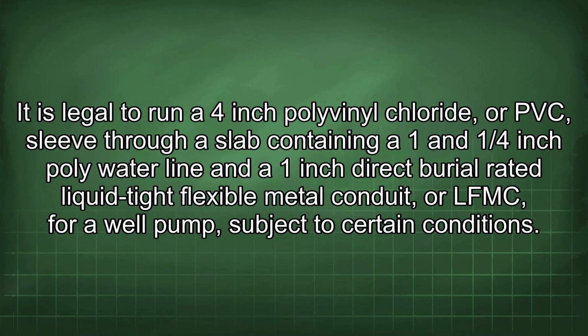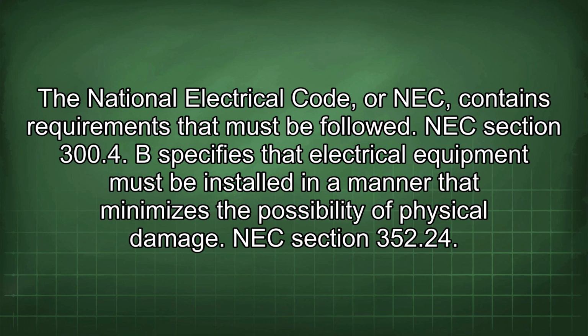It is legal to run a 4-inch polyvinyl chloride, or PVC, sleeve through a slab containing a 1 and 1/4-inch poly water line and a 1-inch direct burial rated liquid tight flexible metal conduit, or LFMC, for a well pump, subject to certain conditions. The National Electrical Code, or NEC, contains requirements that must be followed.